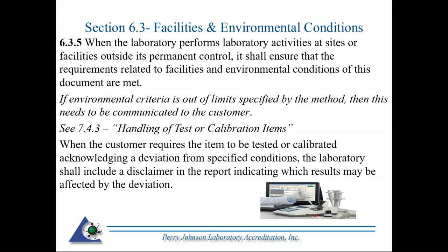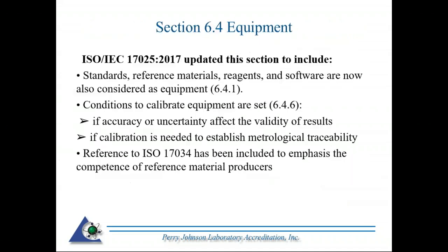in those particular instances, the organization is obliged to bring this deviation, be it out of temperature predefined limits, to the customer's attention and gain their approval before proceeding with the calibration or test. And also it needs to be documented on the report as far as which results may have been affected by the deviation. Okay, I believe that's the end of section 6.3. Not a whole lot of changes in there, except that last one that we just went over.